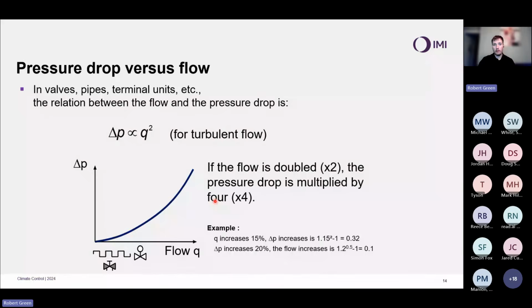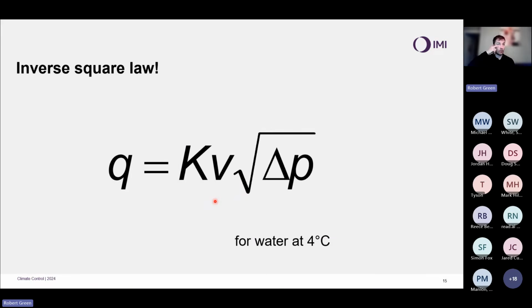And we can apply that as a general rule. And this is the inverse square law. So this is a simplified version of the relationship of flow and differential pressure of any component in a system under turbulent flow, where flow is in meters cubed per hour and differential pressure is in bar. We can say that the flow is equal to the Kv.